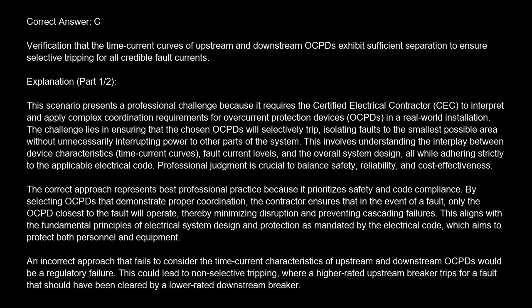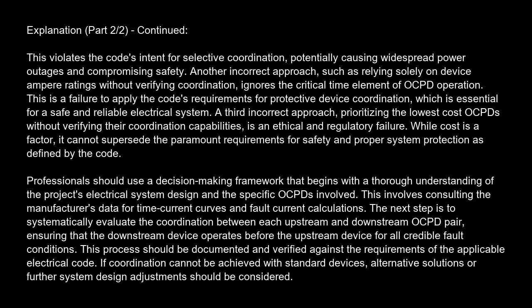An incorrect approach that fails to consider the time-current characteristics of upstream and downstream OCPDs would be a regulatory failure. This could lead to non-selective tripping, where a higher-rated upstream breaker trips for a fault that should have been cleared by a lower-rated downstream breaker. This violates the code's intent for selective coordination, potentially causing widespread power outages and compromising safety.